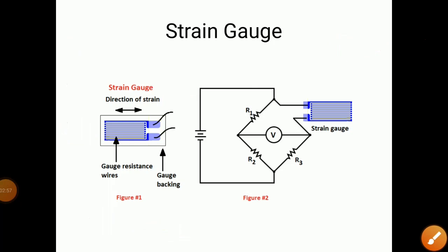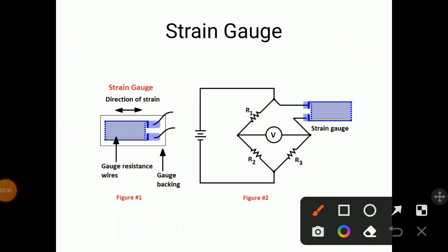This change in resistance is measured in a Wheatstone type bridge circuit. This bridge circuit has four arms: R1, R2, R3, and R4. In arm number 4, strain gauge is connected. As this resistance changes, there will be some change in voltage observed. As force is applied, resistance changes, and because of this, voltage produced also changes. This is the indication of applied load — applied load is converted into voltage with the help of the Wheatstone type bridge circuit.